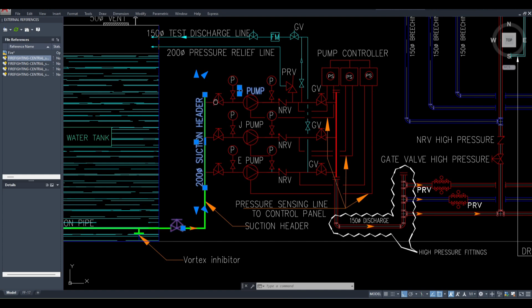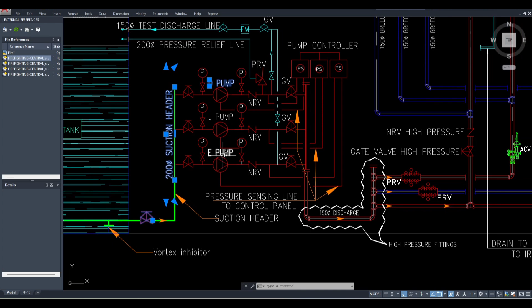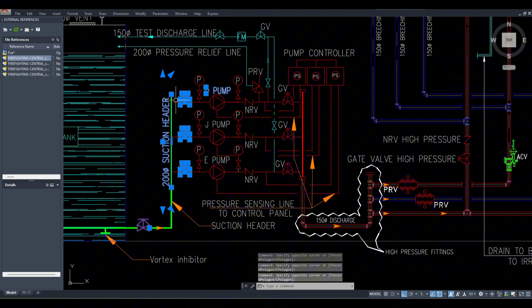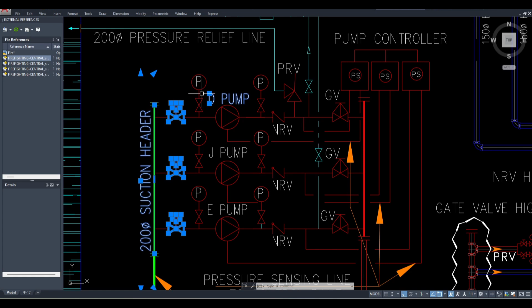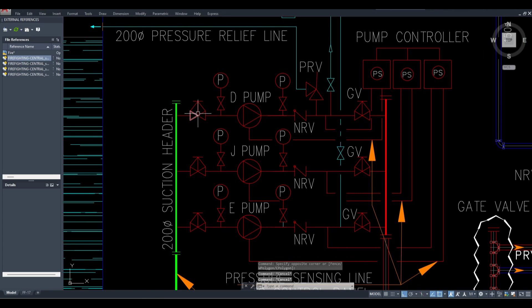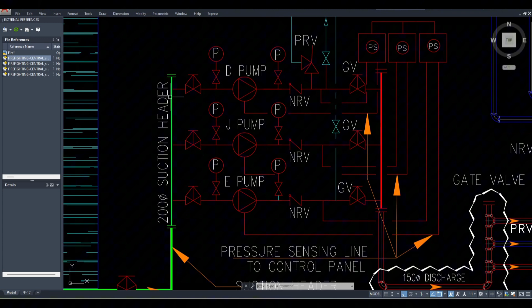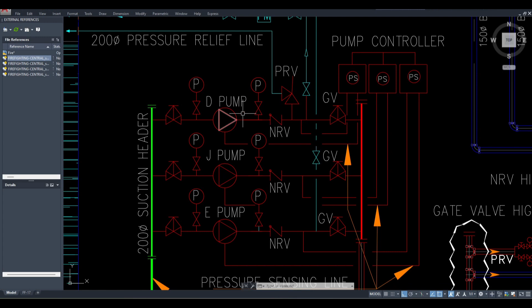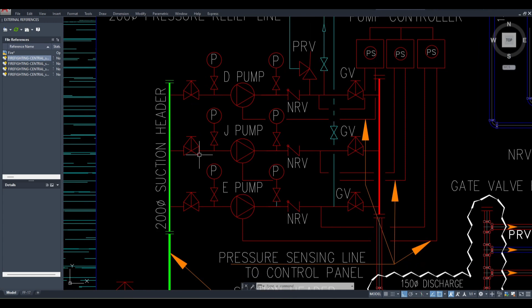Then, for each pump to work independently, it first needs to be isolated, so each must have one isolation valve: one here, one here, and one here. Each also has a pressure gauge, which is connected through its own isolation valve, so anytime you want to repair, you can close it and repair or change whatever is needed. The isolation valve means we can isolate that part of the system for maintenance. So suppose water is ready up to here and we want to maintain this engine, we can close this valve and maintain it, and the water won't go inside, while the other pumps remain open and ready.